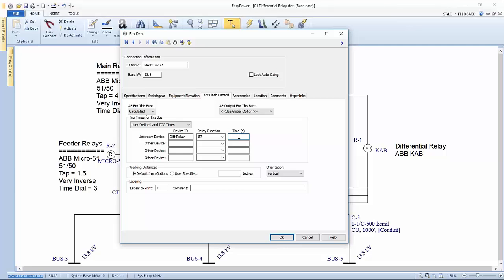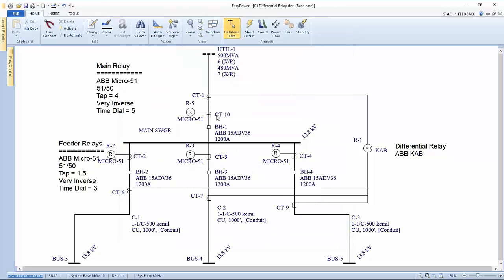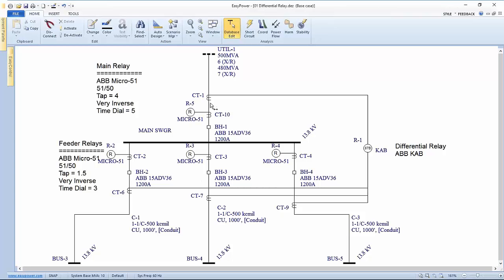The time that's put in here now is based upon the manufacturer's allowable settings or whatever adjustments are set up for the trip of the breaker once the fault condition has been determined. These can be relatively fast. Let's say in this case, it's going to be 0.083. Because the tool doesn't know specifically, even though we're sensing the downstream elements, it doesn't know anything beyond the fact that there's a difference between the input and the output of the zone of protection.